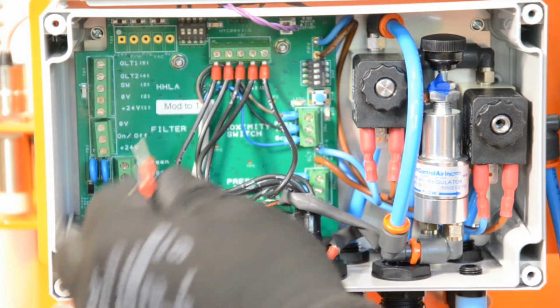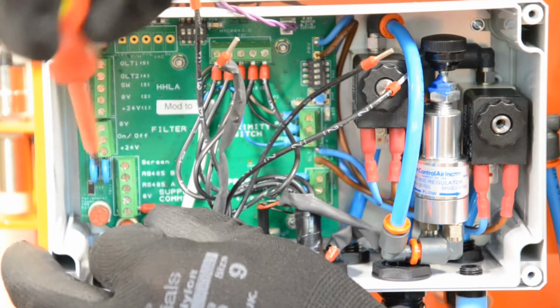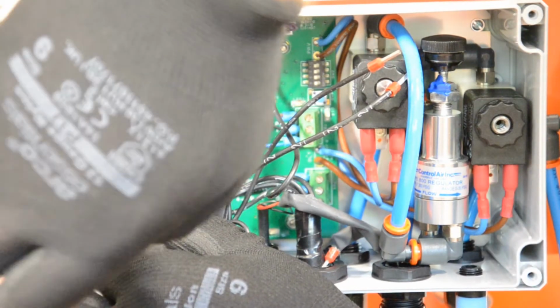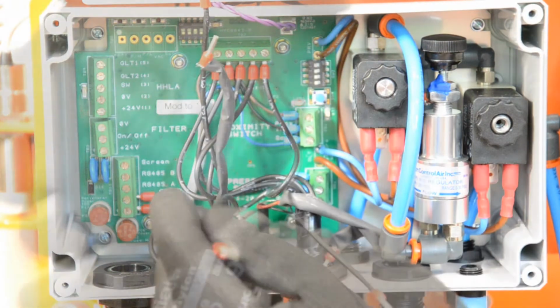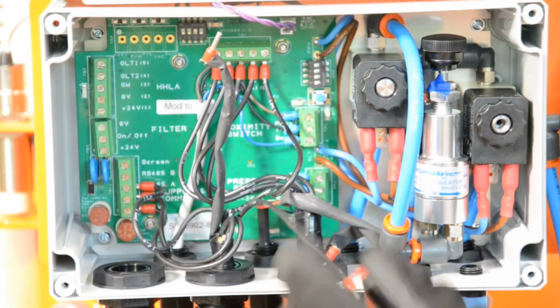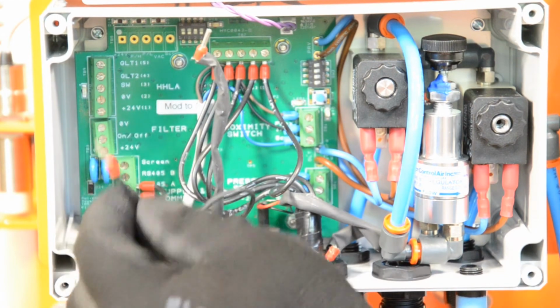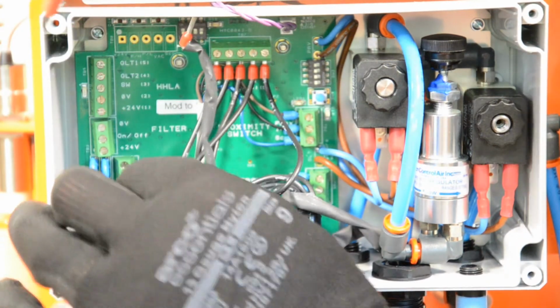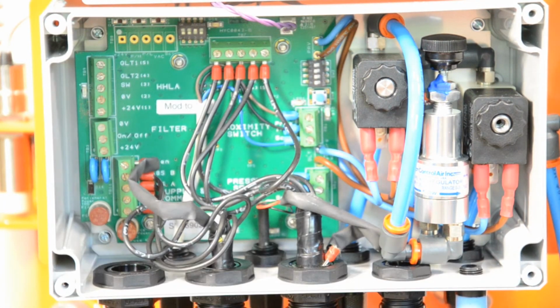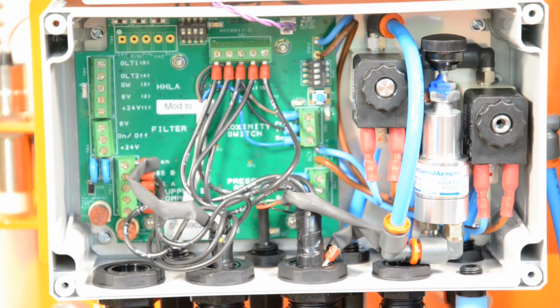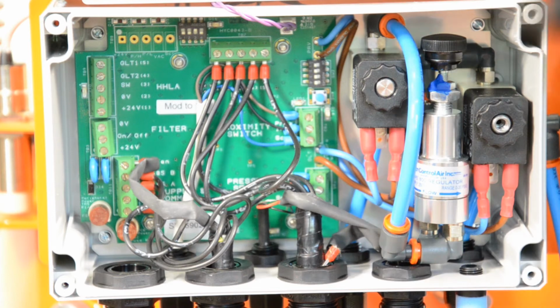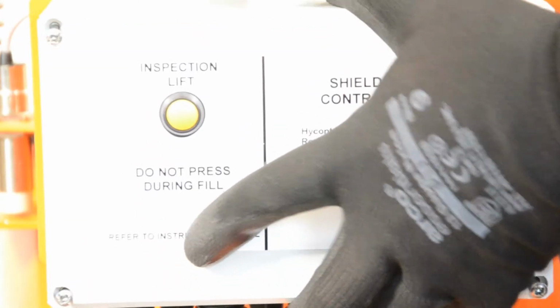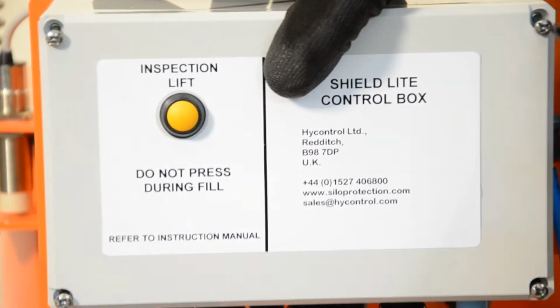Put the comms cable through the second port and wire into the terminal block on the bottom right. Wire 1 goes to 24 volts, 2 to 0 volts. The serial communications wire number 3 goes to RS485A, wire 4 to RS485B, and the screen wire goes to number 5. Note that, unlike the level probe, both ends of the screen must be connected for the panel. This completes the silo top wiring with the exception of the filter control.